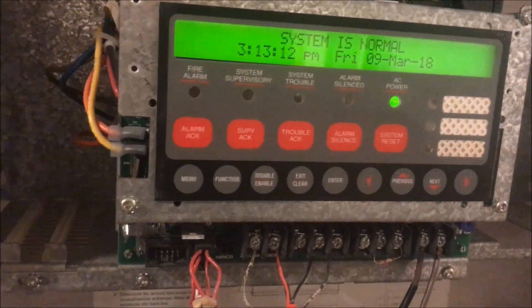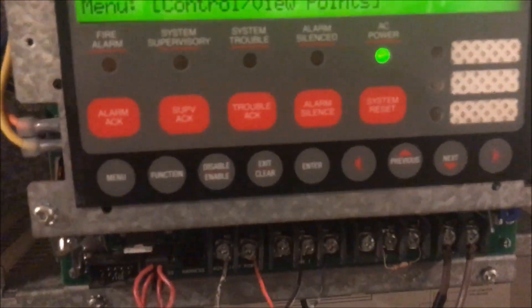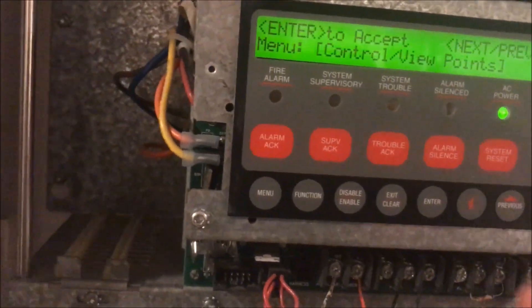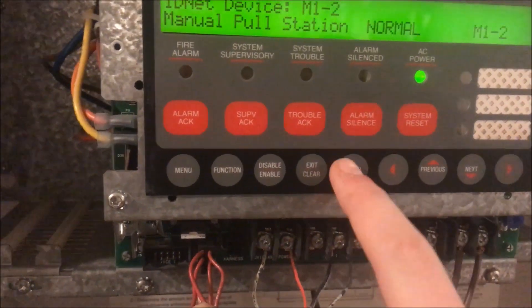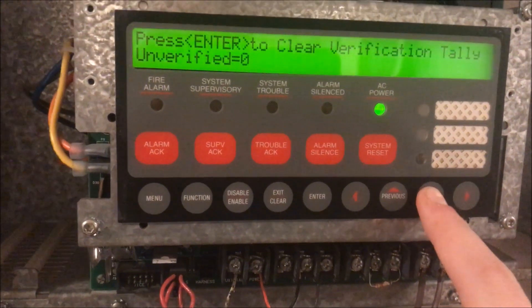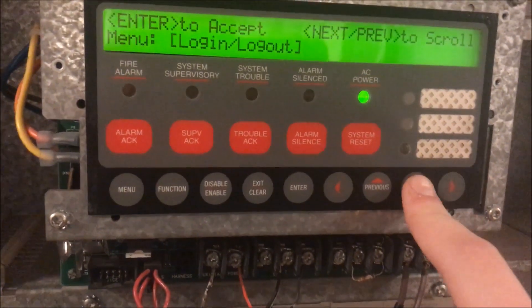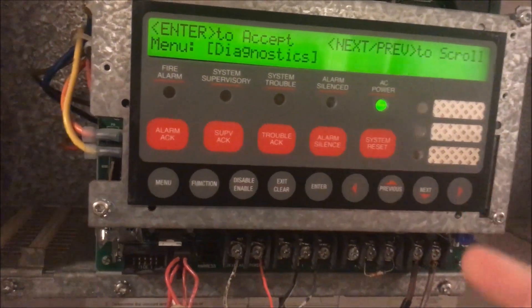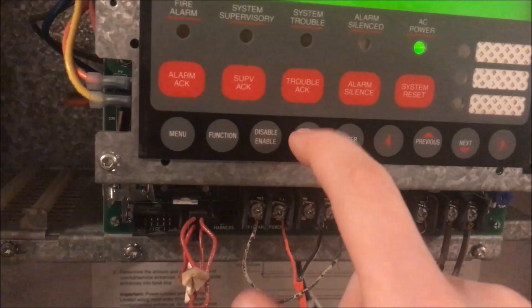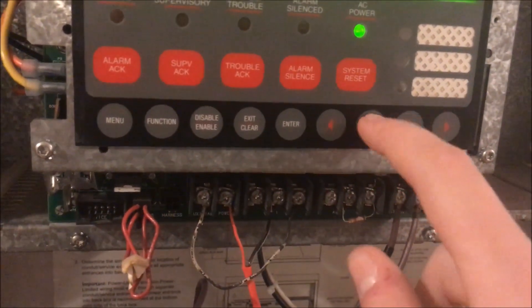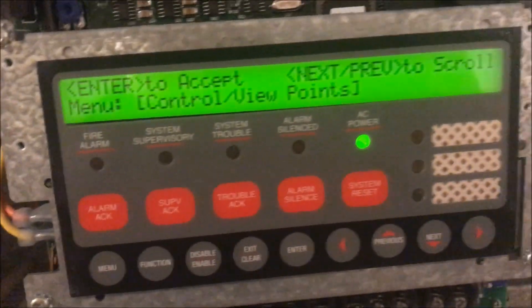Also in level one you can acknowledge alarms, acknowledge supervisory, acknowledge trouble, silence alarms, and reset the panel — all right there in your emergency operating instructions. You can also view points; for example, looking at a pull station, you can't disable or enable it, you can basically just see how it's doing. You can also log in, view historical logs, view what software the panel is running, and run a quick diagnostic.